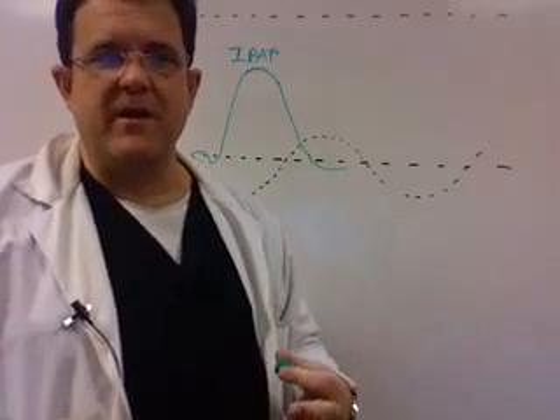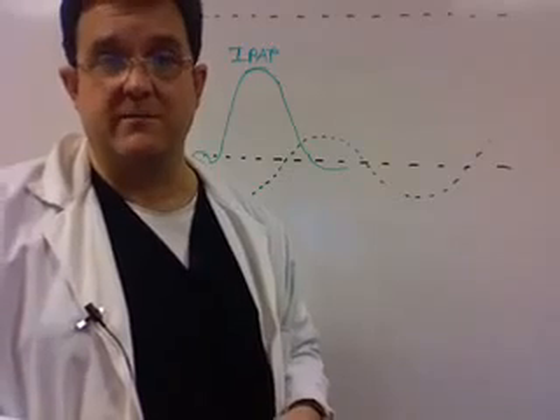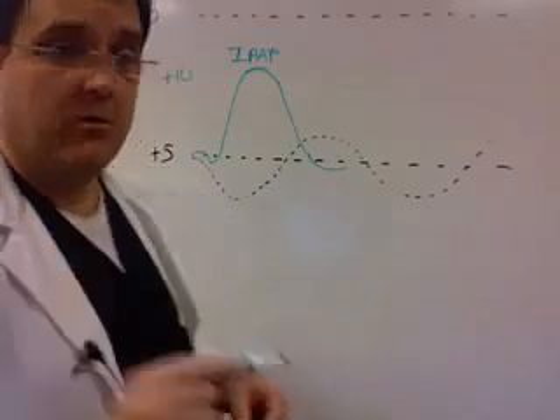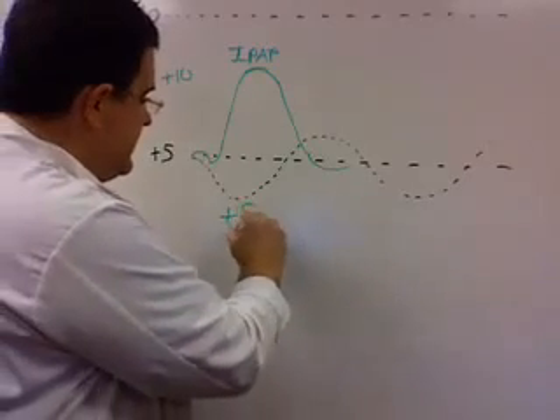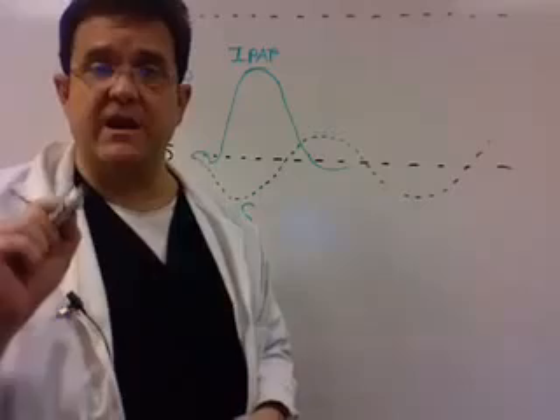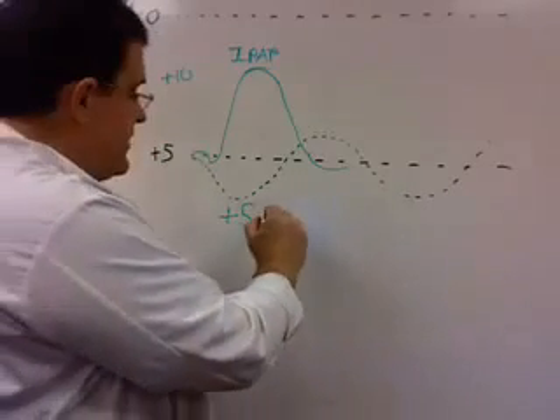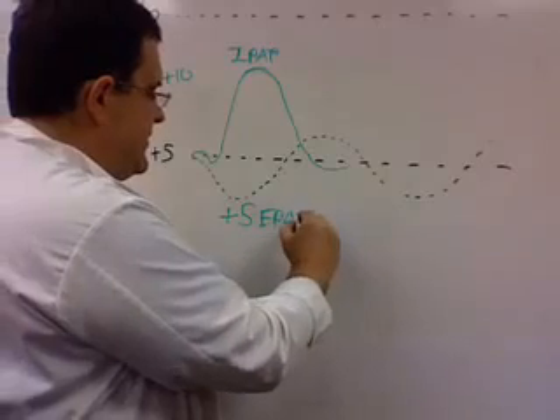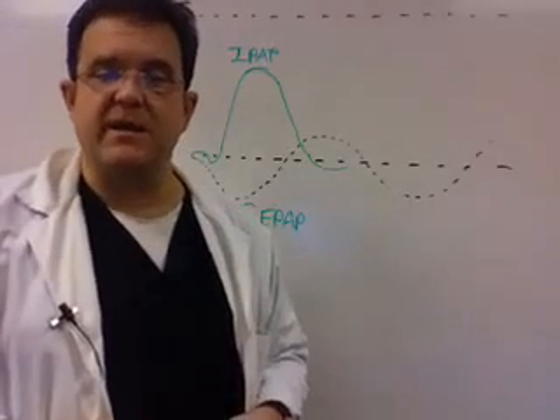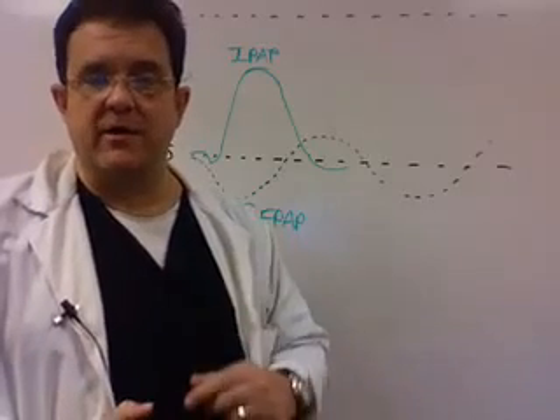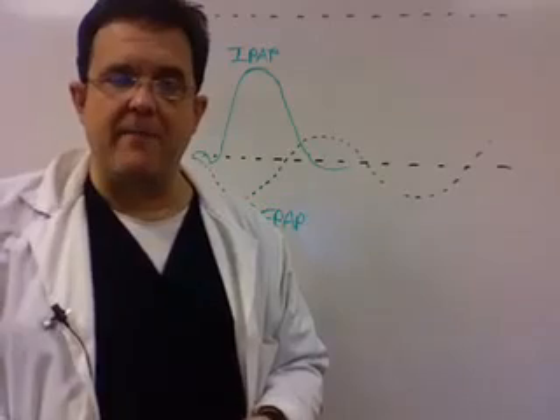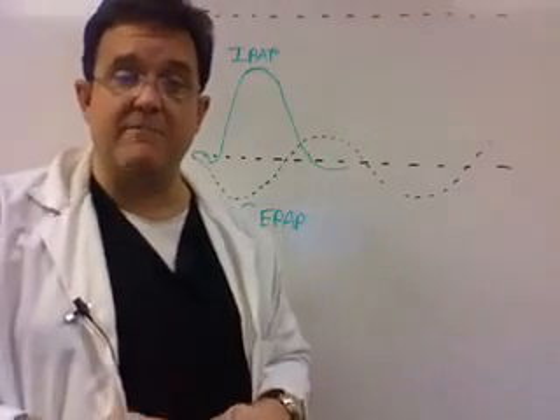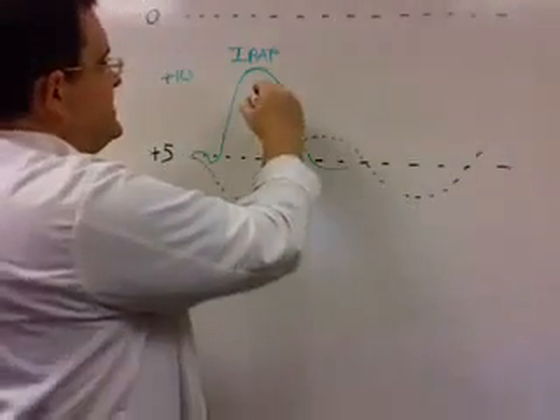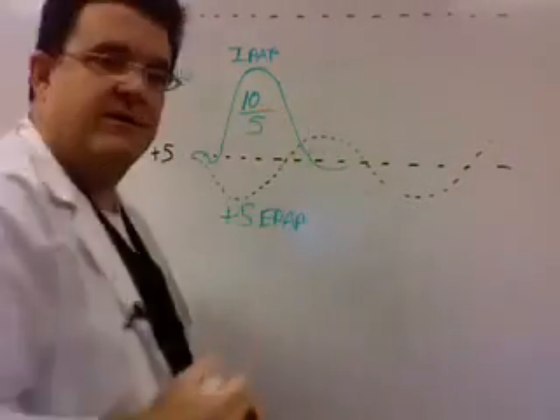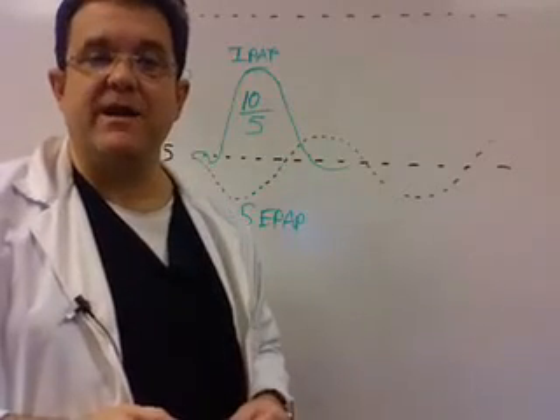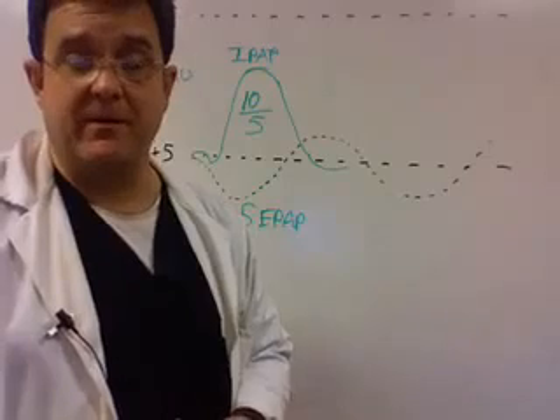You might argue that you're just overcoming the imposed workload of the system by adding a small IPAP. But the rule was this: you must use at least 5 of CPAP. And on the Respironics BiPAP they call it EPAP, expiratory positive airway pressure. You must use at least 5 of EPAP. And then the IPAP must be at least 5 above, and this is general, you might argue with these numbers, but generally the IPAP must be at least 5 above the minimum level of EPAP. So that makes the minimum settings for BiPAP 10 over 5. 10 of IPAP and 5 of EPAP, or whatever you want to call it, CPAP or PEEP. It's all basically the same thing.